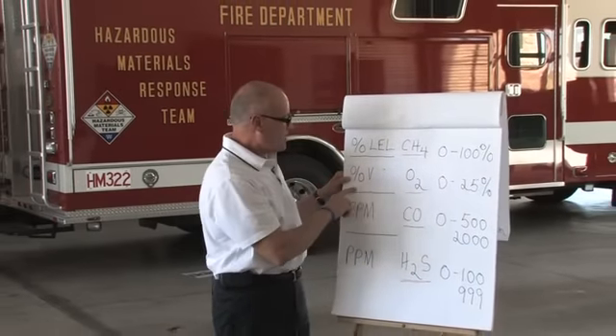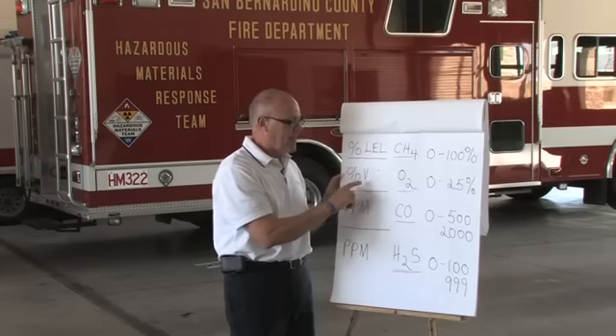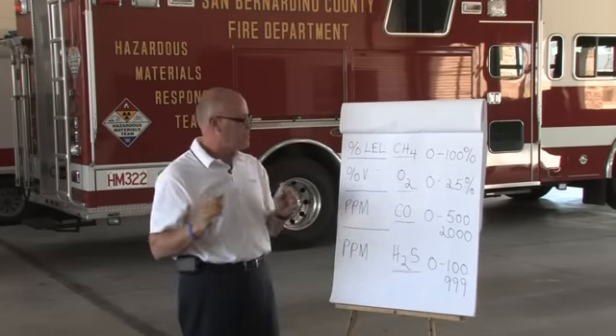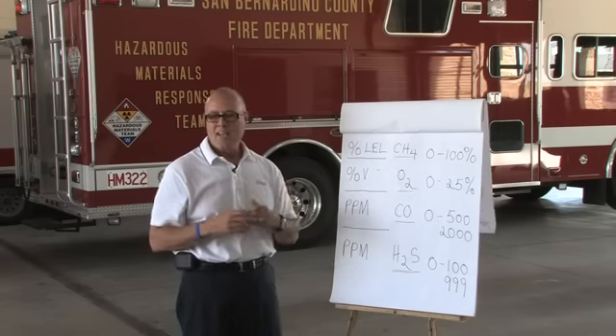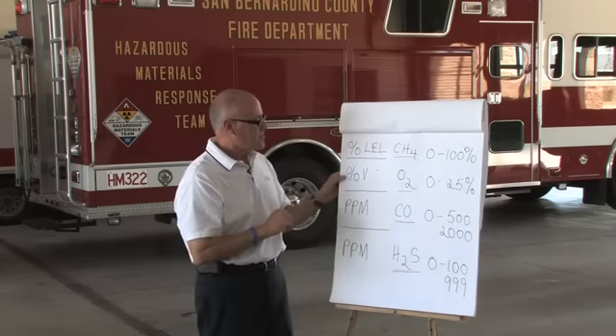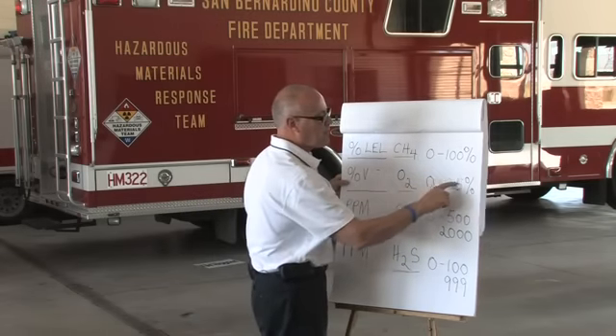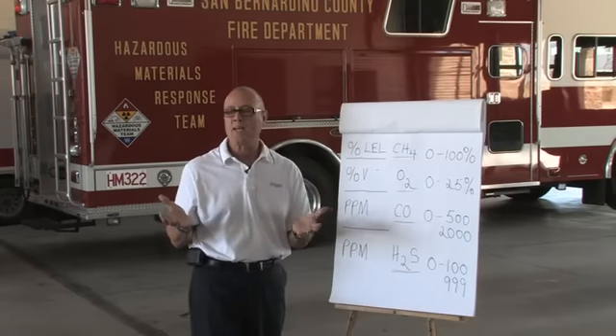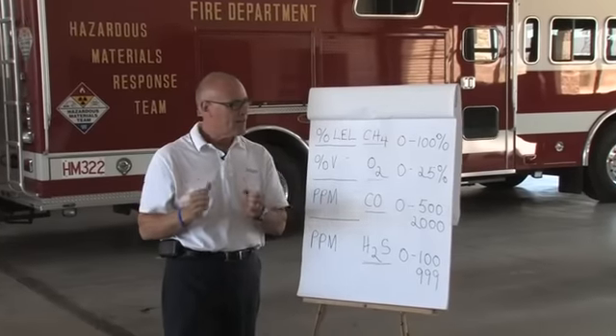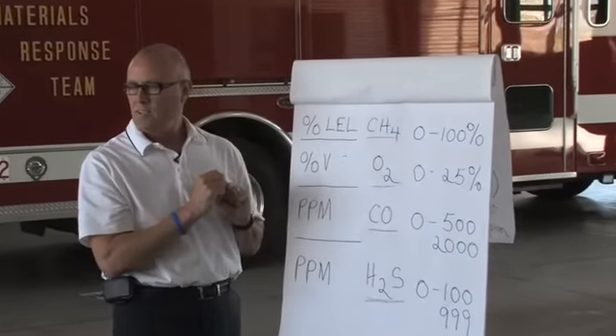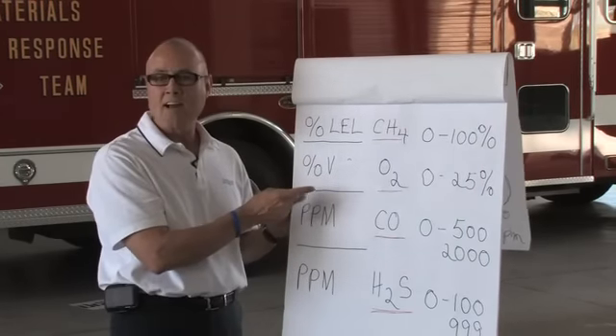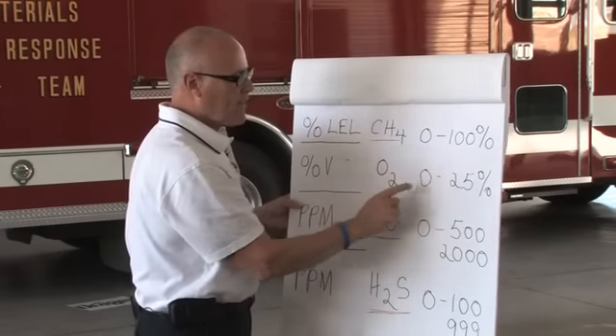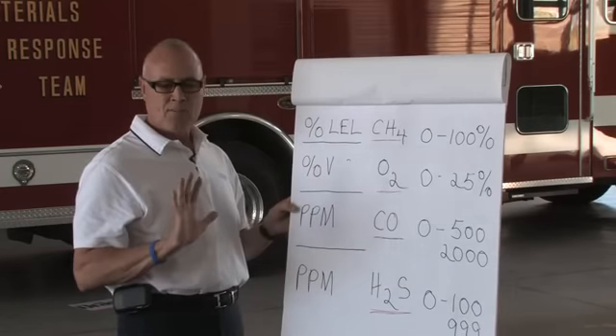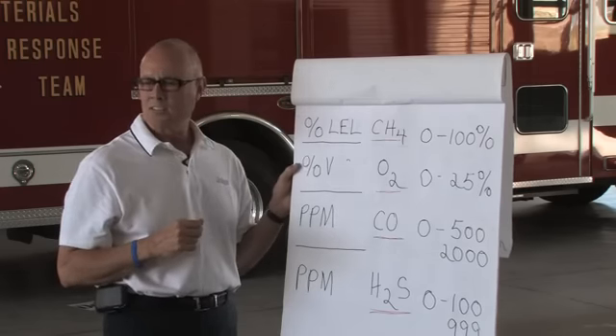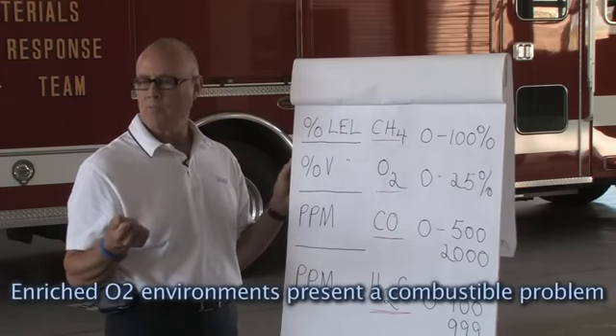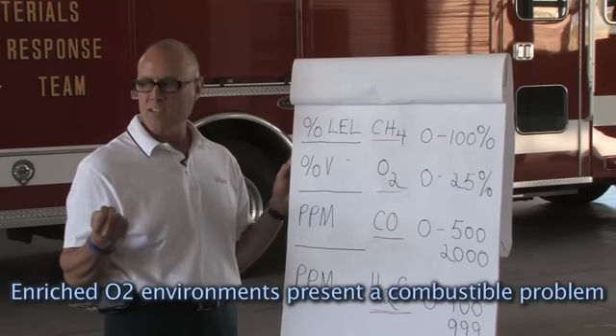Your number 2 scale is oxygen. Percent by volume is what I've noted here, the amount of oxygen per volume of air. Air is basically made up of essentially 21% oxygen and 78% nitrogen. So what we're doing is we're monitoring a scale of 0 to 25%. Generally, in fresh air, we're breathing 20.9% by volume oxygen. Our concerns are if we have a deficiency of oxygen, we need to have an alarm, and that alarm will come at 19.5%. But we're also concerned about enrichment, and that's why our scale goes to 25 from 20.9. If you see your oxygen starting to increase, you know you've got an oxygen enrichment problem, which poses a combustible problem for you. It enhances combustion. So a lot of oxygen in the environment is not a good thing.